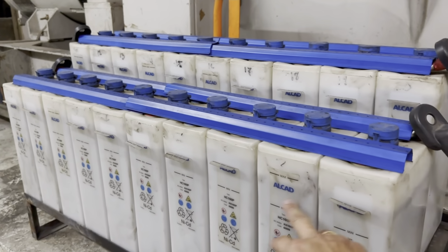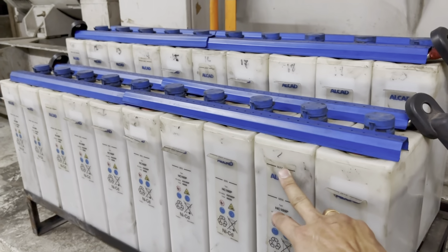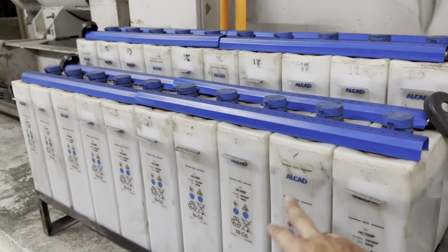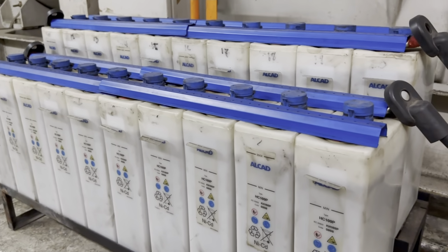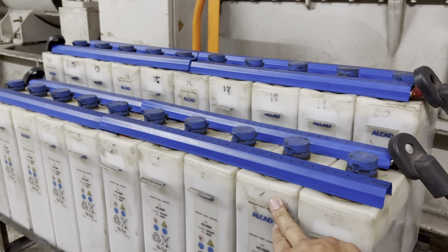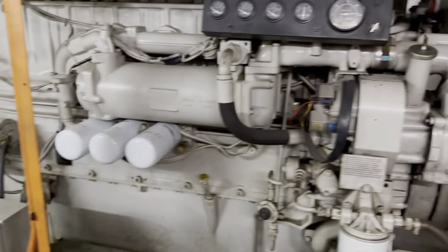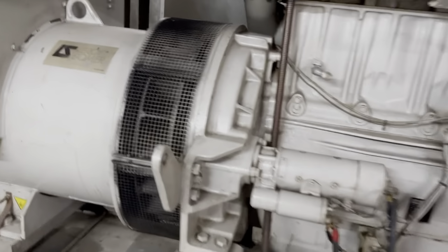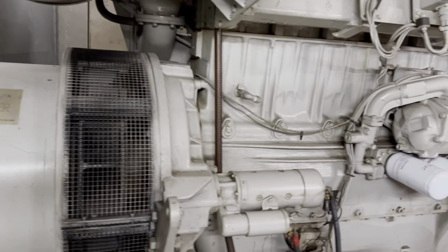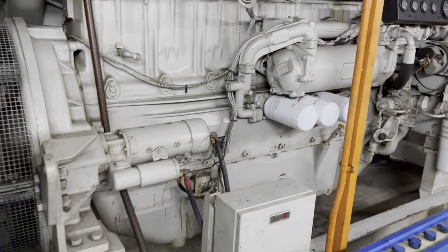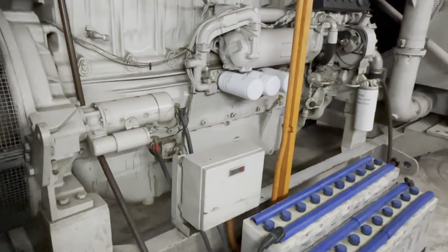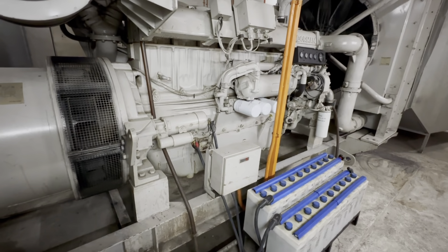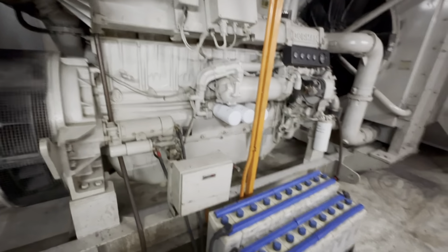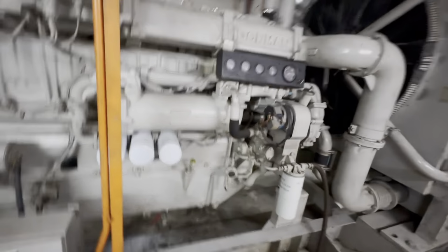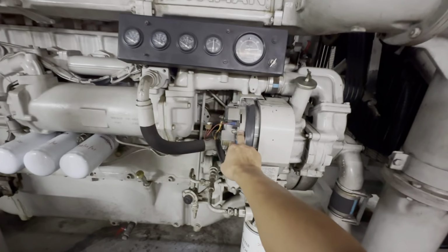Eventually, the voltage here will drop from 28 volts. If it drops to, say, 20 volts, maybe 19 or 18, it won't have sufficient voltage to power up the solenoid, fuse solenoid, and any other timer relay or relay. The genset AMF panel will then have a breakdown in voltage, and the whole genset system will break down, causing the genset to stop automatically. So always take note and check whether this alternator is charging or not.